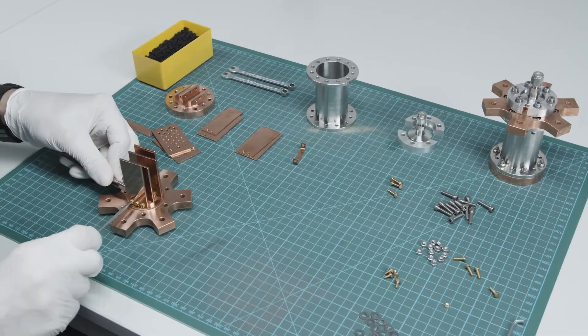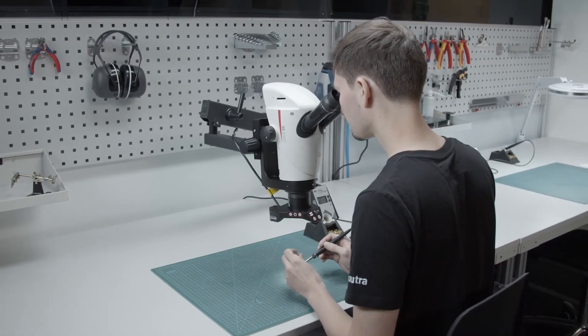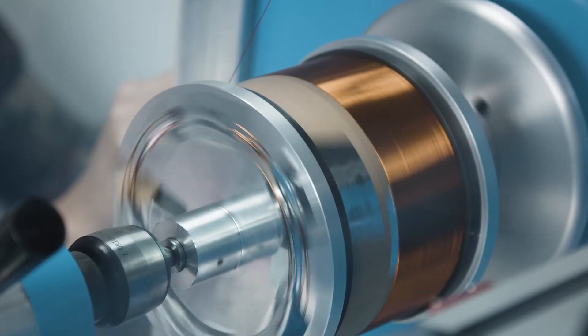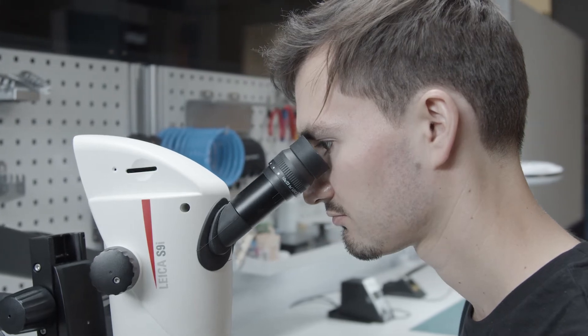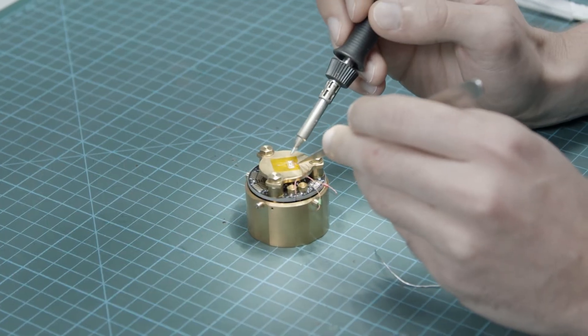One of our main components in the cryostat system is a superconducting magnet. These are created in-house using our high precision coil winding machine and our vacuum casting system. With the winding machine you can set a precise number of layers of superconducting cable to your coil. The vacuum system enables the correct ratio of resin and the correct temperature and pressure. When you put in a lot of effort and work precisely, you end up creating a good product — it's very rewarding.